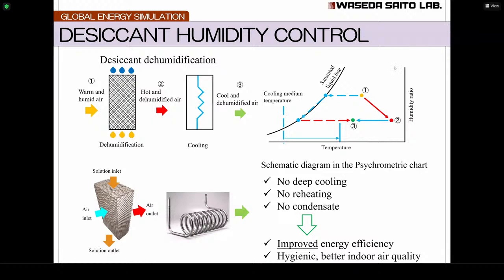So this is a psychrometric chart. Here first, warm and humid air is coming, and in this dehumidification process, air is dehumidified, but the temperature increases because this process is a heat release process. That's why we have to cool that with a cooling process. But the important point is that in conventional mechanical dehumidification, the air is cooled too much, to 0 degrees Celsius or something like that. But in this process, we only have to cool down to about 15 degrees Celsius or something. So the system performance increases greatly, and with no reheating, we can improve the energy efficiency greatly, and we can get hygienic, better indoor quality.